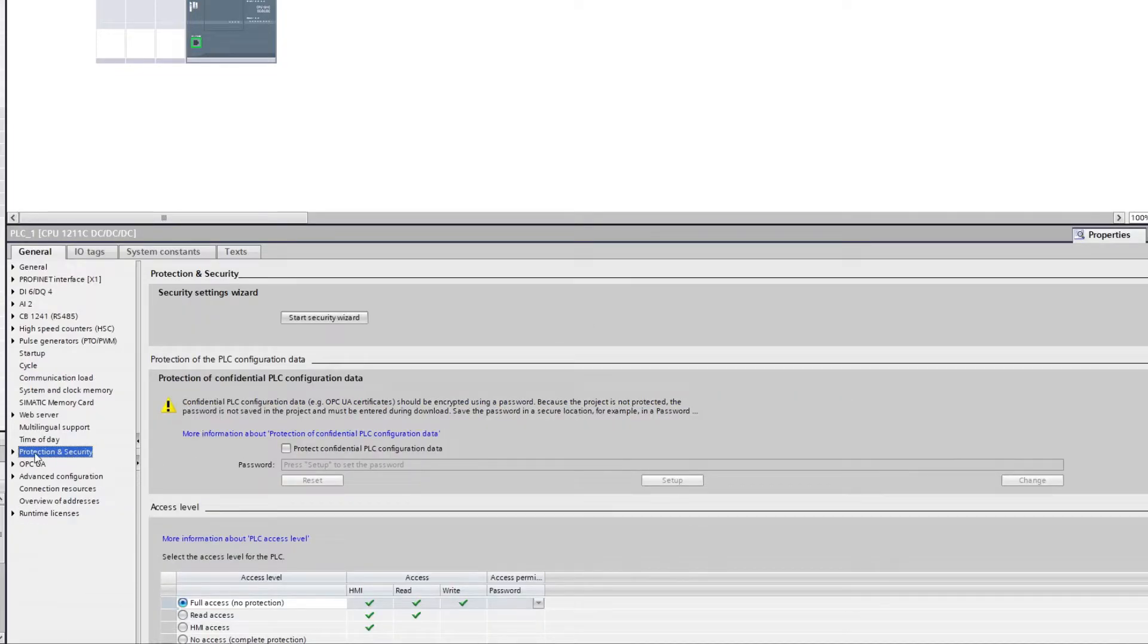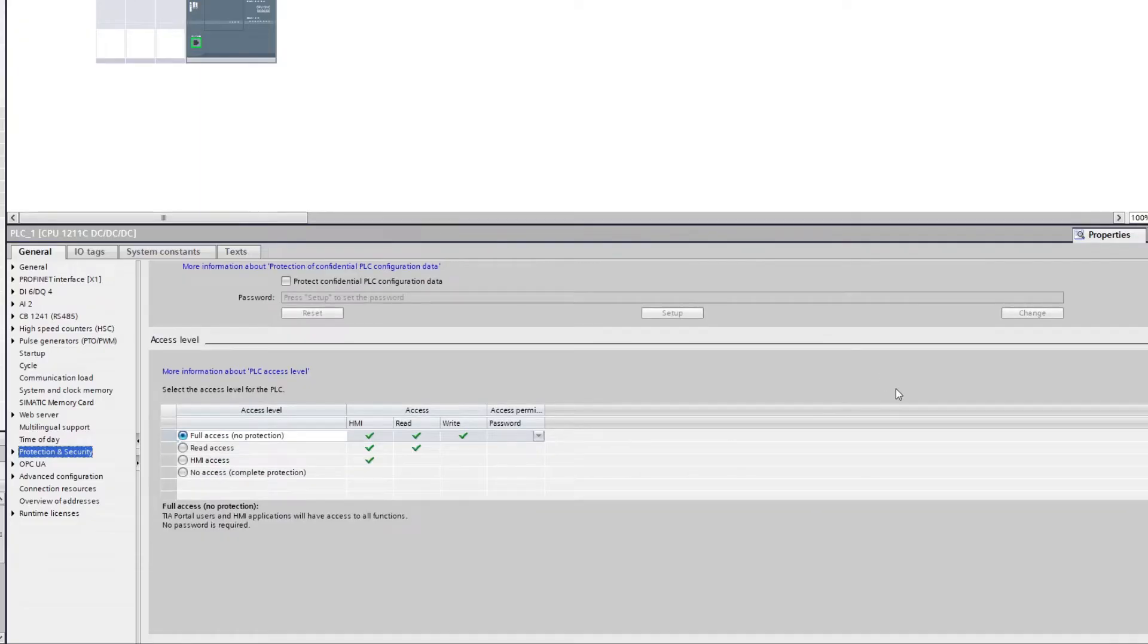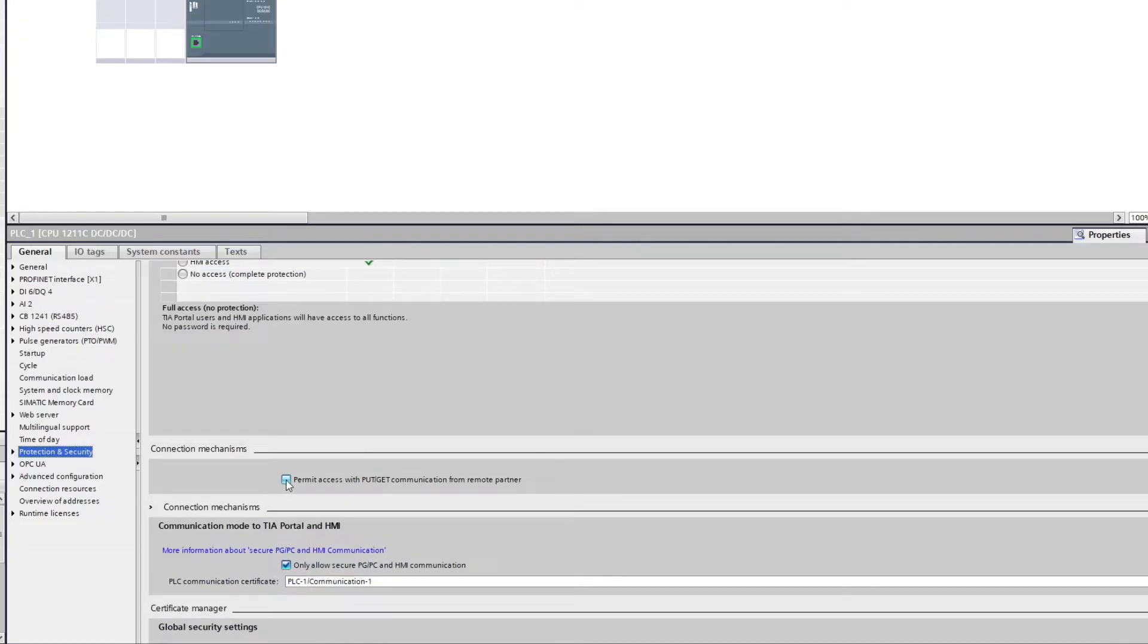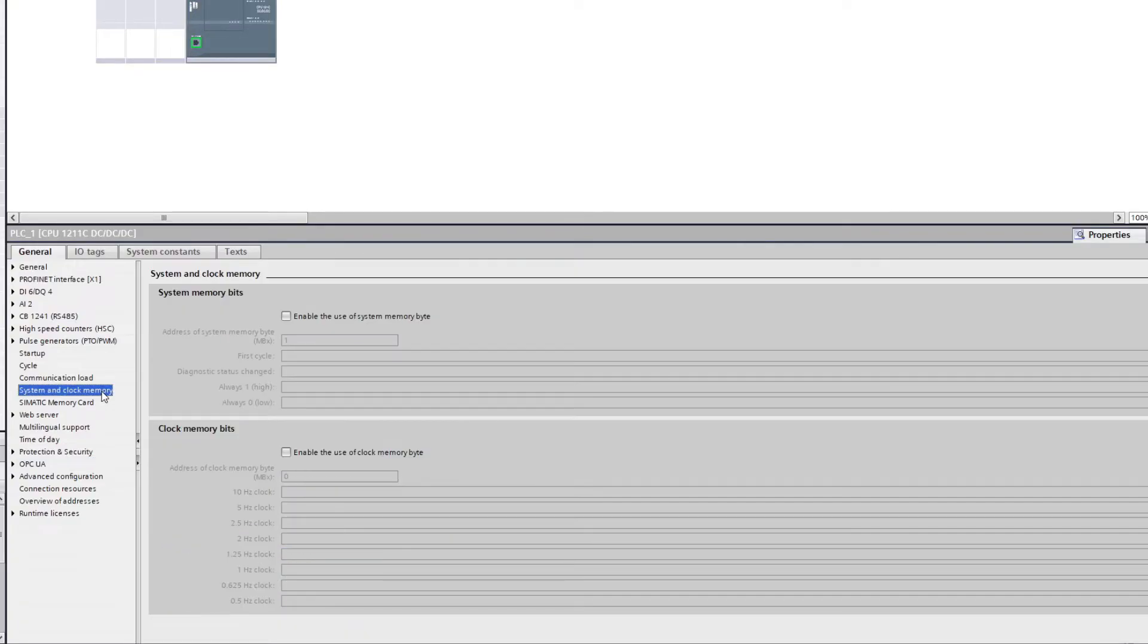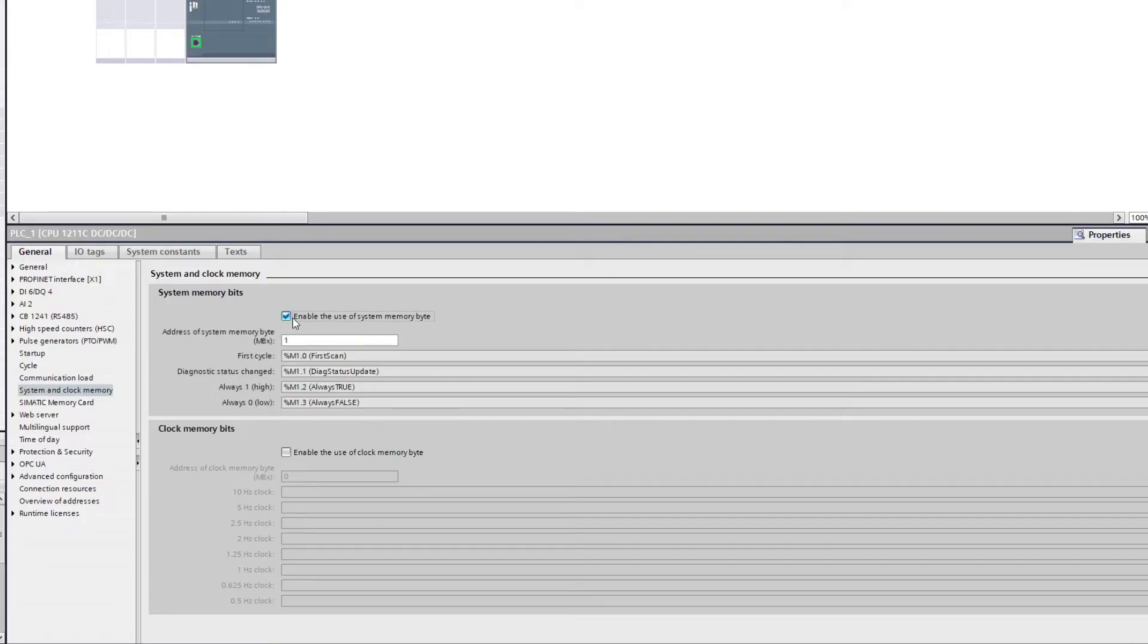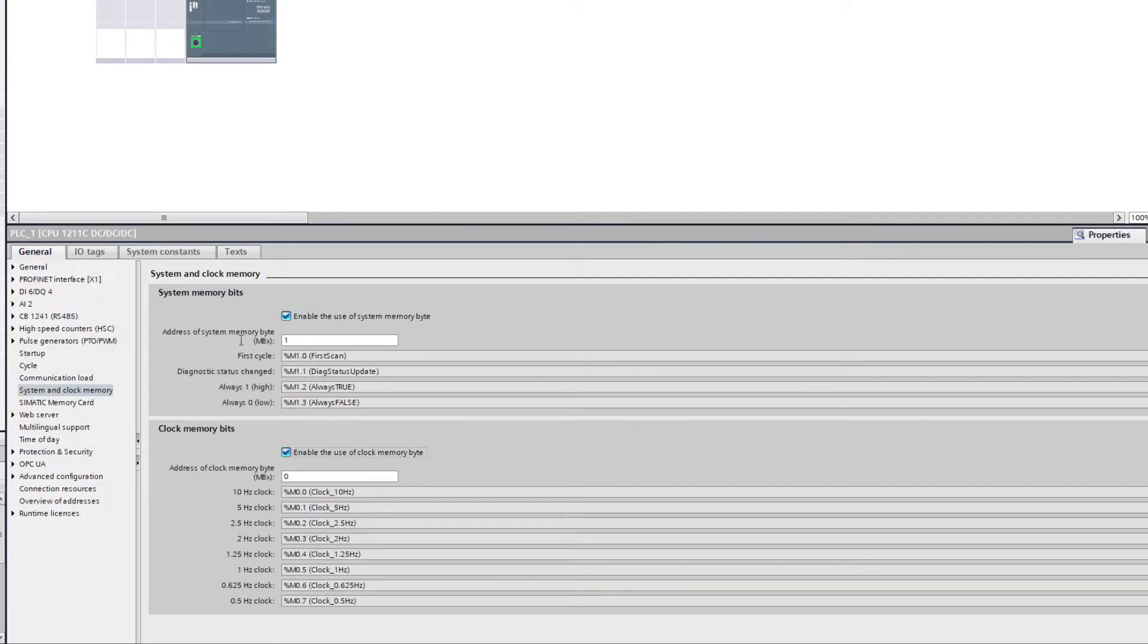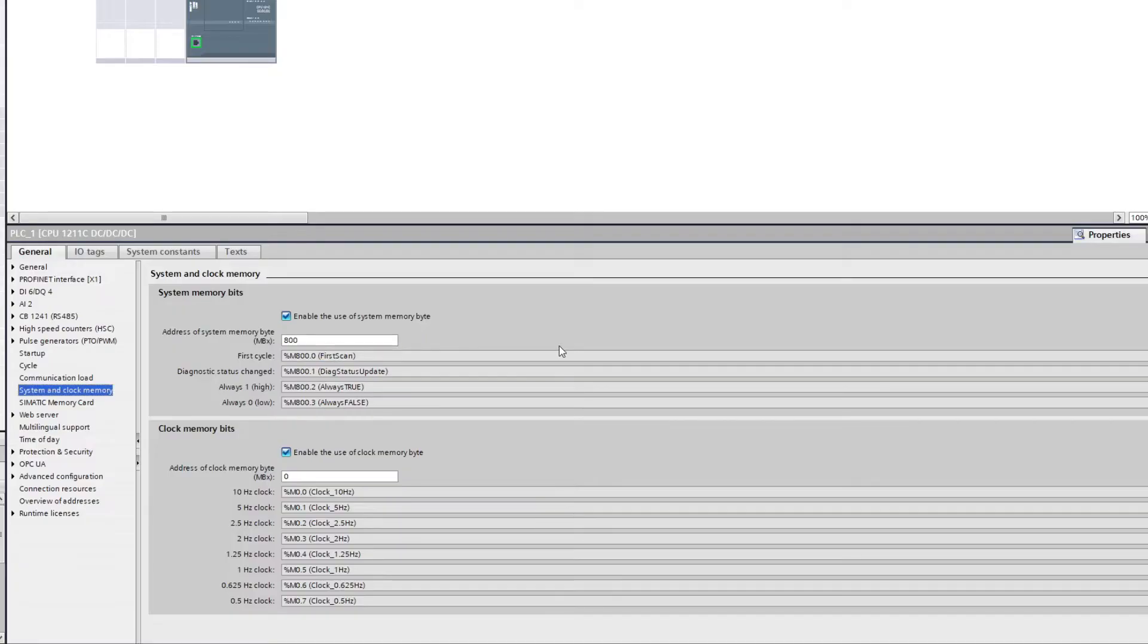If we then scroll down a bit we will find a box to check that says permit access with put get communication from remote partner. Then we want to go to system and clock memory and enable both system memory bits and clock memory bits. I will use the memory by 800 and 801 so it won't collide with any other memory bits.